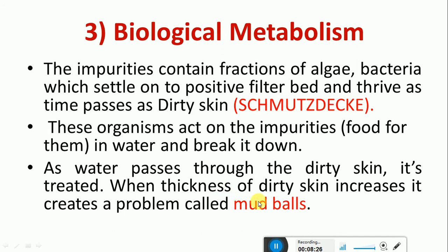When the thickness of this dirty skin increases, it creates a problem of mud balls. This has to be taken care of by removing the top layer of sand during maintenance and operation of the sand filters. However, this is also one of the processes in the theory of filtration.